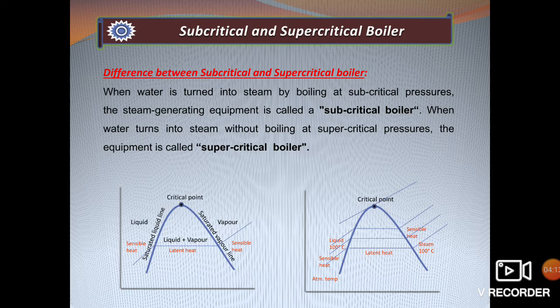In a subcritical boiler, as the name suggests, operation is below the critical point. There will be exchange of latent heat, and there will be a mixture of liquid and vapor phases, which need to be separated with the help of a drum. So in a subcritical boiler, there is always a drum attached, which contains a cyclone separator. The function of this separator is to separate the saturated steam from the mixture of liquid and vapor. The operating pressure in a subcritical boiler is always less than the critical point.